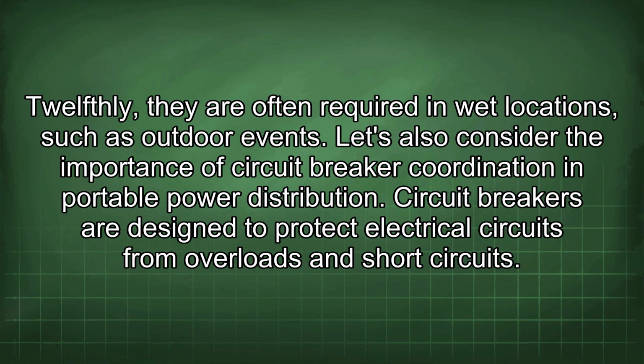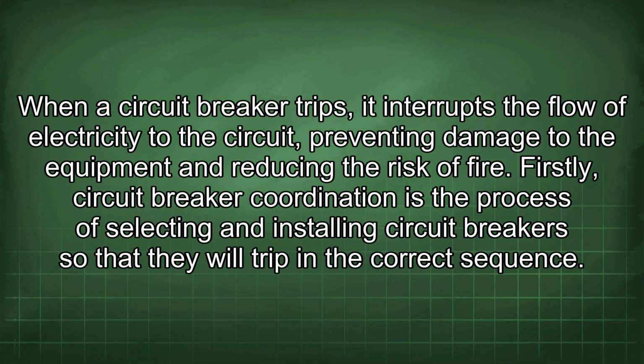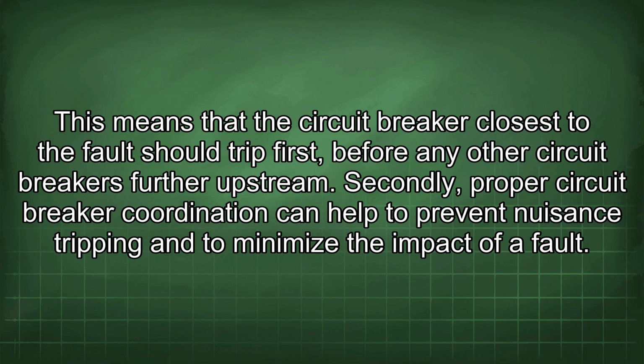Let's also consider the importance of circuit breaker coordination in portable power distribution. Circuit breakers are designed to protect electrical circuits from overloads and short circuits. When a circuit breaker trips, it interrupts the flow of electricity to the circuit, preventing damage to the equipment and reducing the risk of fire. Firstly, circuit breaker coordination is the process of selecting and installing circuit breakers so that they will trip in the correct sequence. This means that the circuit breaker closest to the fault should trip first, before any other circuit breakers further upstream.